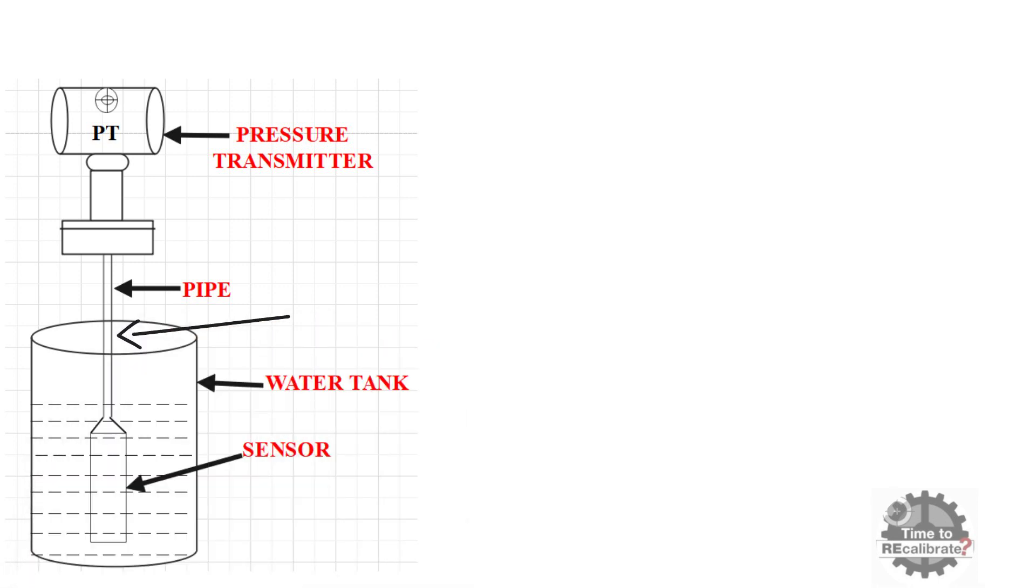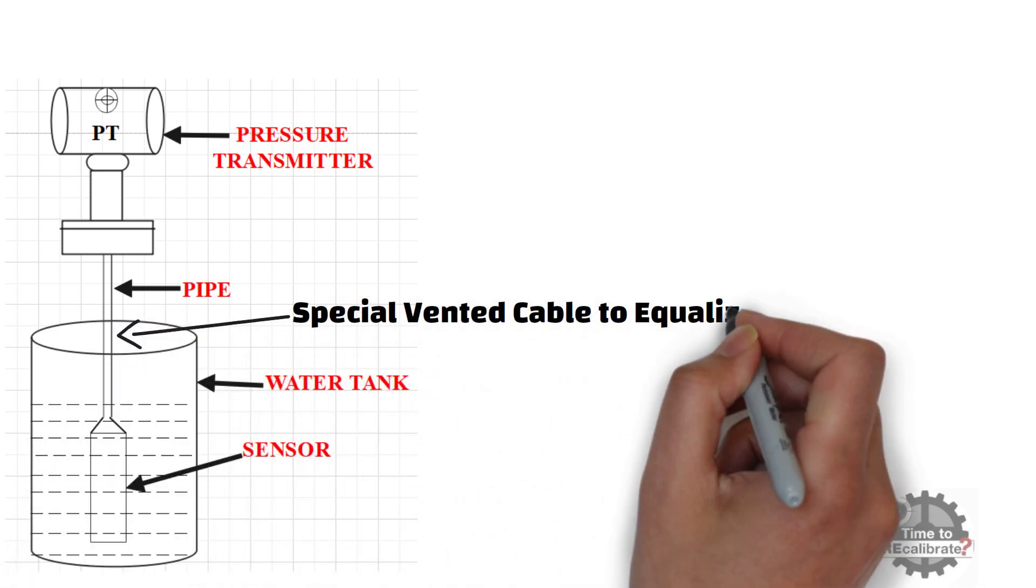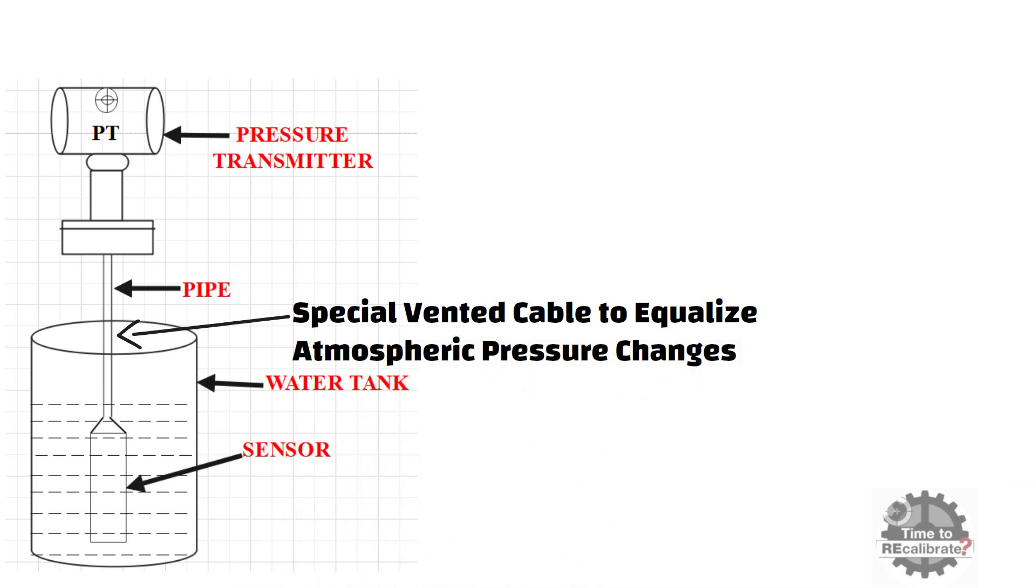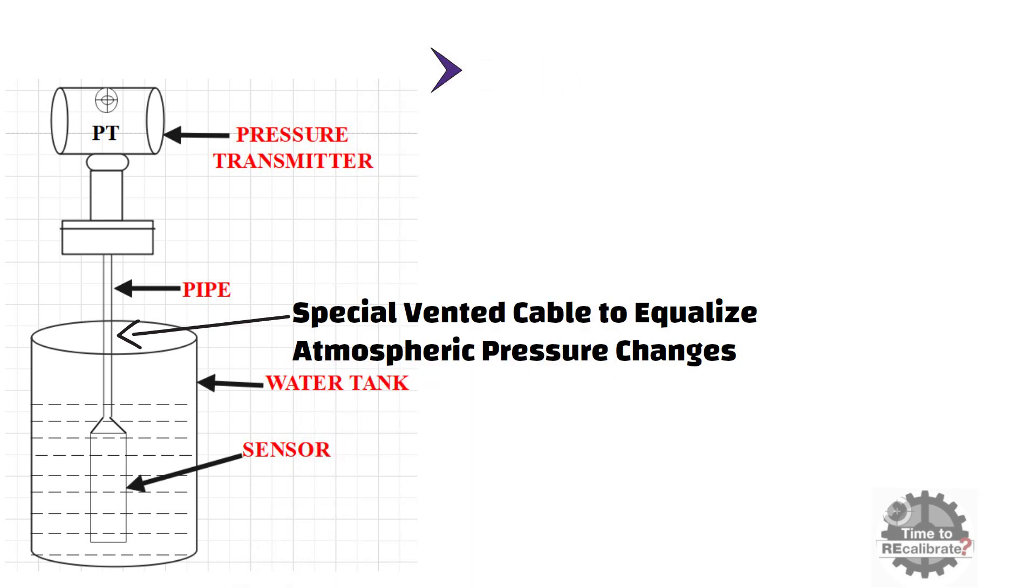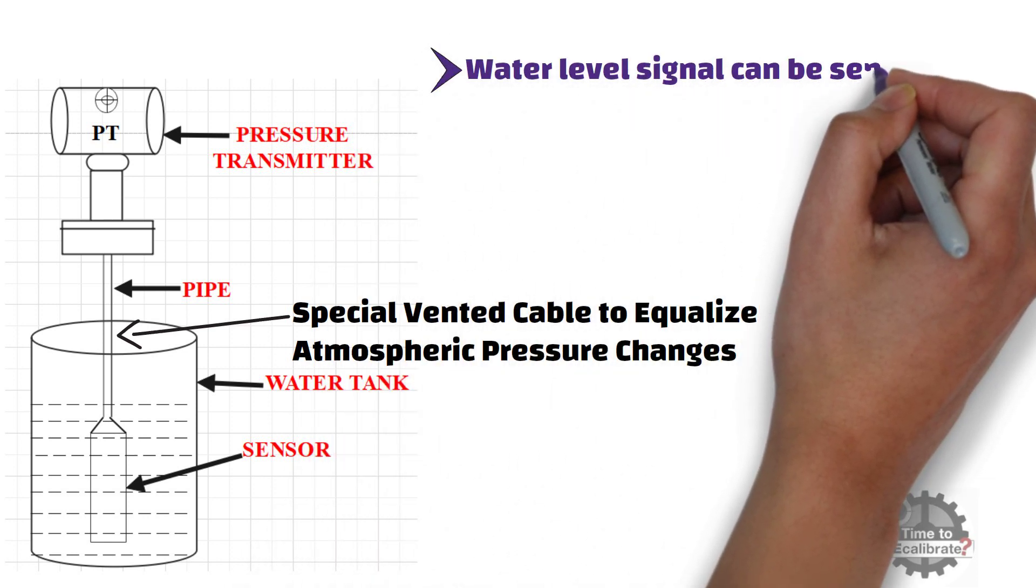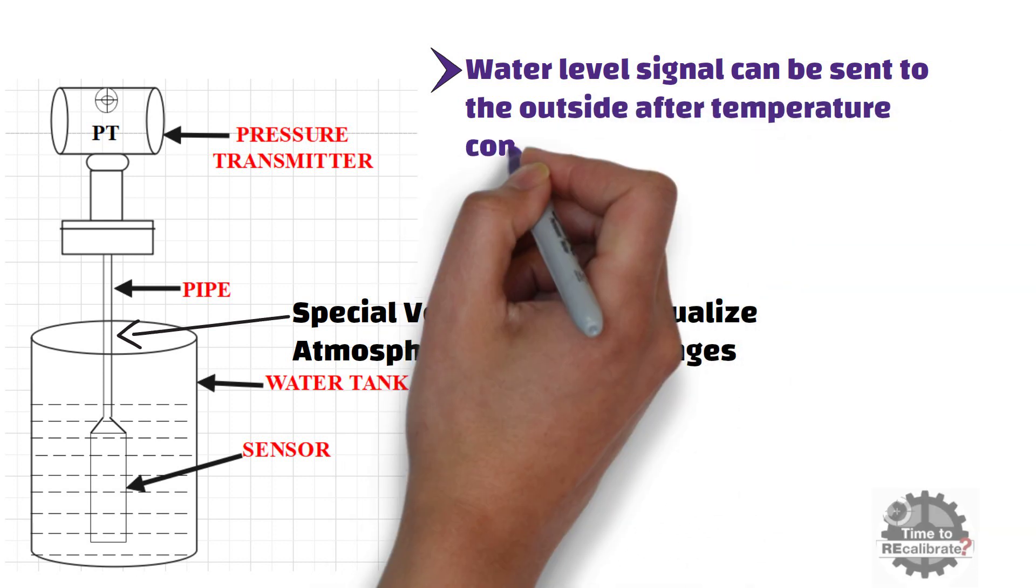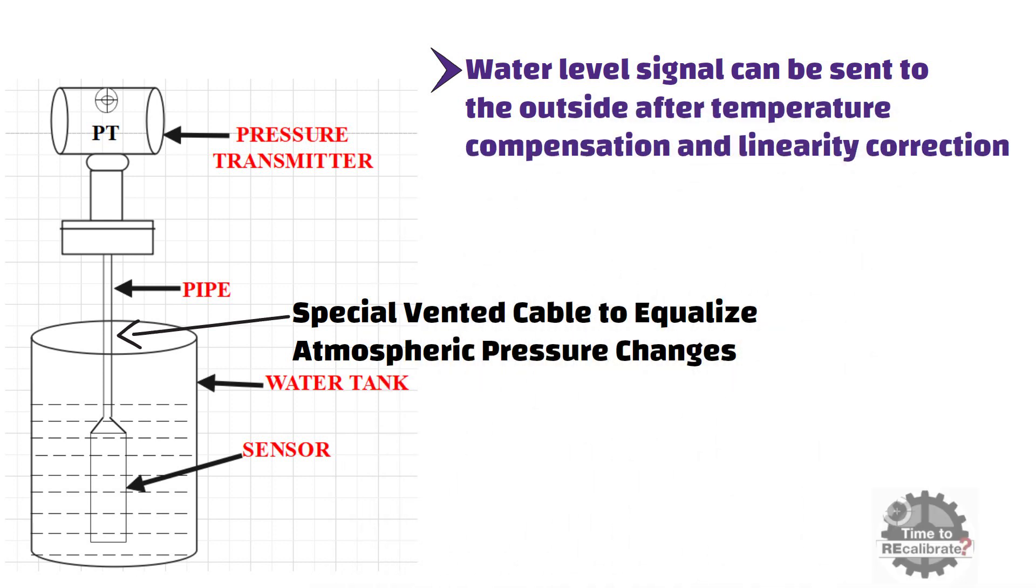Submersible pressure transmitter comes with a special vented cable to equalize atmospheric pressure changes, so it accurately transmits the measured liquid level to the transmitter. Water level signal can be sent to the outside through a standard current signal of 4 to 20 milliamperes after temperature compensation and linearity correction.